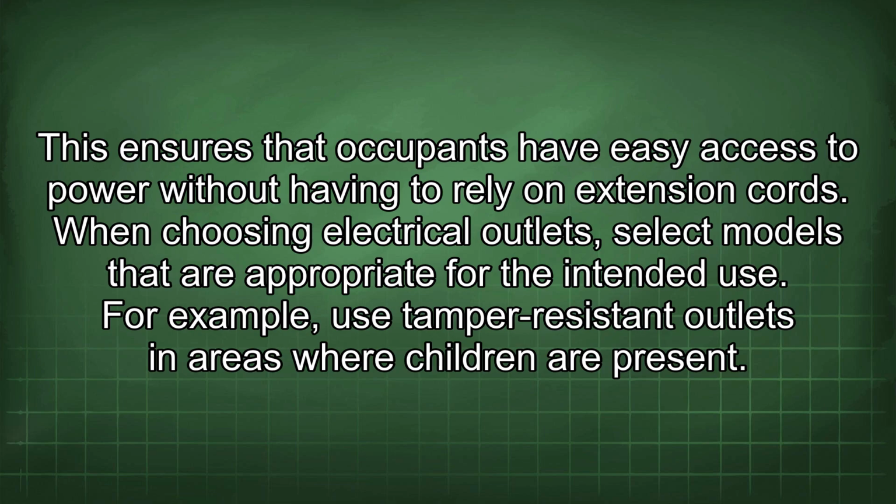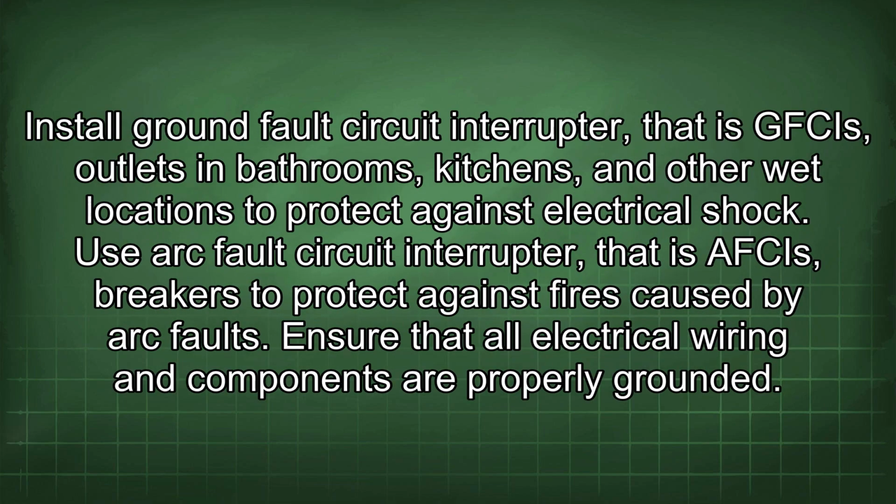When choosing electrical outlets, select models that are appropriate for the intended use. For example, use tamper-resistant outlets in areas where children are present. Install ground fault circuit interrupter, that is GFCI, outlets in bathrooms, kitchens, and other wet locations to protect against electrical shock. Use arc fault circuit interrupter, that is AFCI, breakers to protect against fires caused by arc faults.